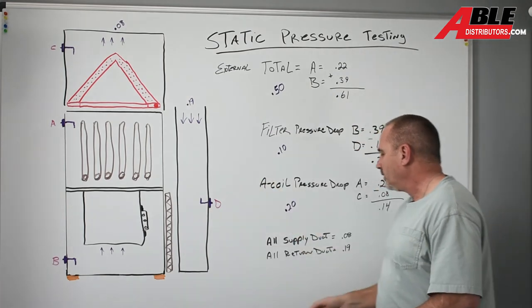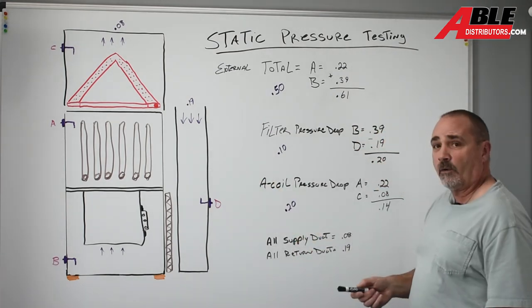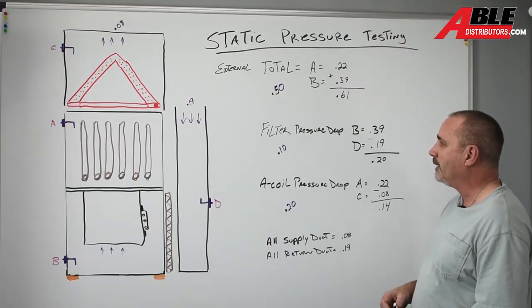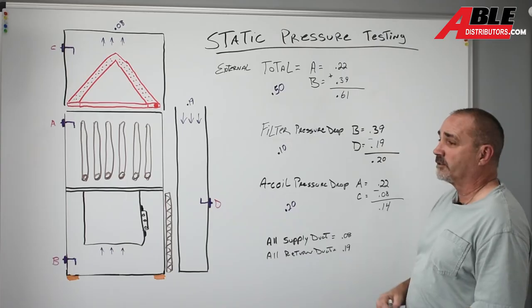So on this, all the supply duct work turned out to be 0.08 static. All the return duct, 0.19, I think that's a little high. And the total is 0.61, which again is high.